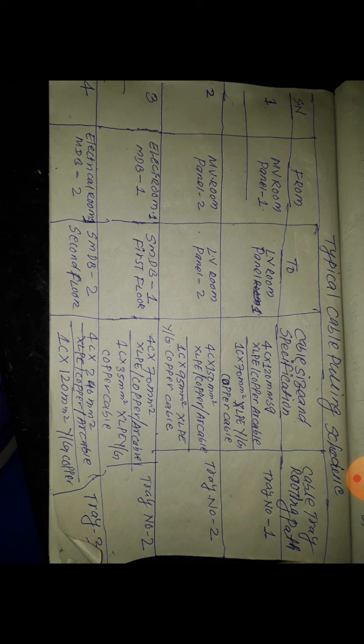So the second cable is coming from MV Room panel number 2 and going to LV Room panel number 2. The cable size is 4 core 150 mm square, and this is also the same XLPE copper armored cable. This means the insulation type is XLPE, the conductor is copper, and it is an armored cable. It goes to tray number 2, and the earthing cable also needs to follow this value.